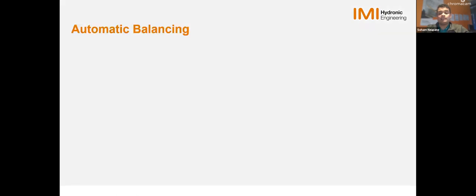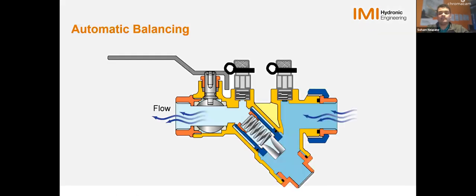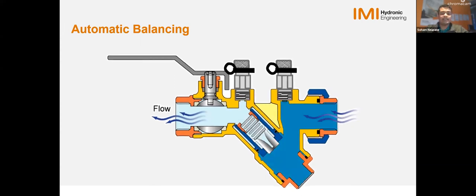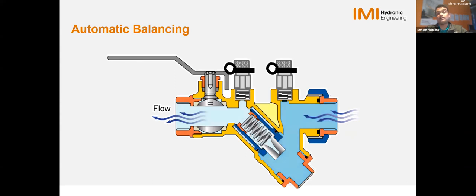And while in operation, this is what it's doing. When you see some pressure changes, your spring is either going to retract or contract there. And then, depending on the pressure change, it's constantly adapting the opening. As you can see, the CV keeps adjusting and ensures that you have that set flow despite the pressure changes. And that's how it takes care of interactivity, okay?